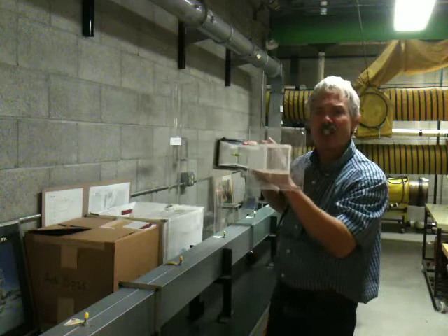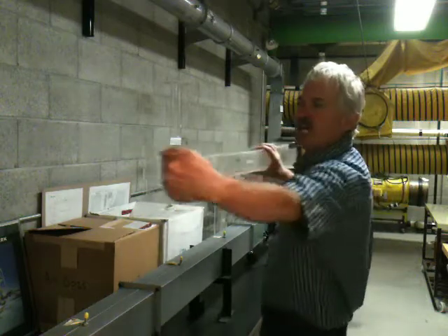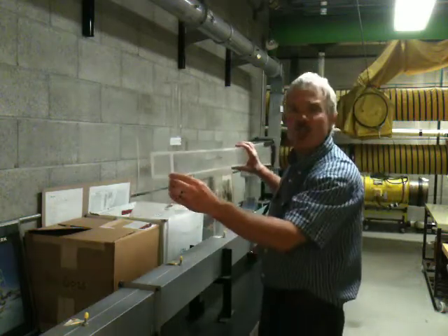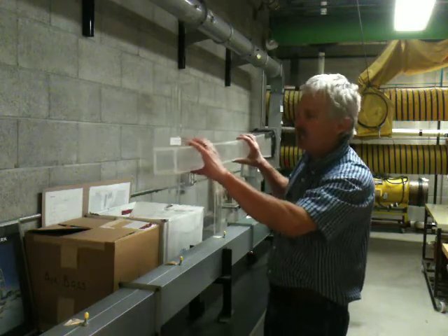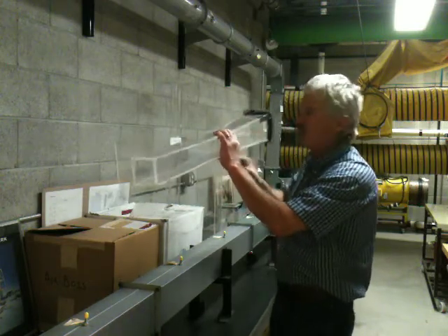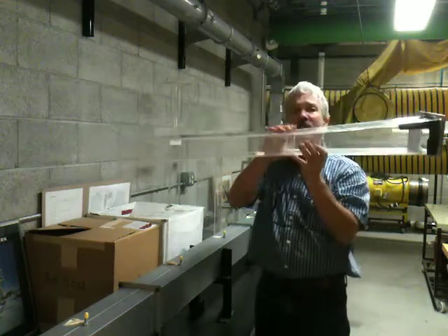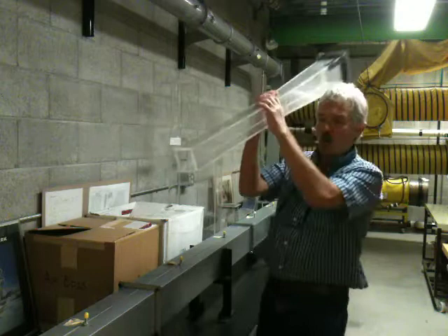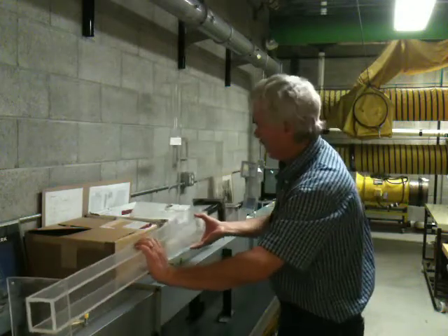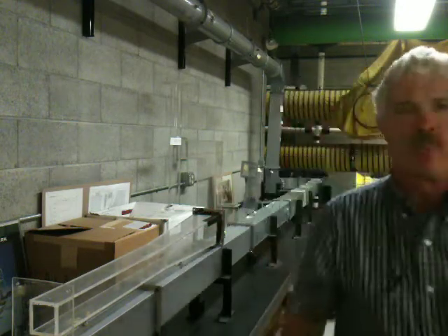Then we're going to swap this 180 degrees so the air will enter from the original duct. It's going to experience a sudden contraction. It will flow through the smaller duct here, and then it will go through a gradual expansion back to the original size duct. So again, the concept of airflow changing, resulting in shock loss. We can study 4 different types of shock loss with this one test section.